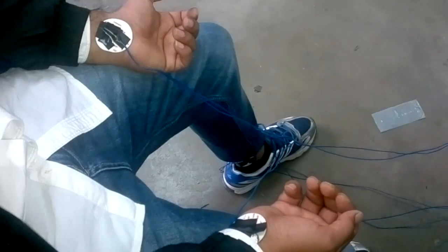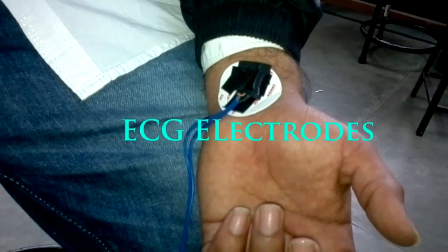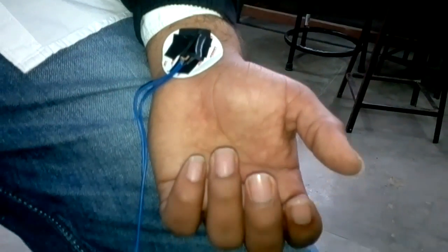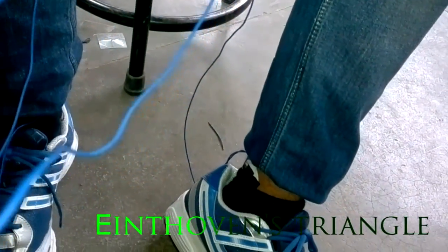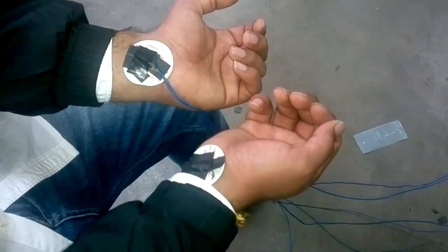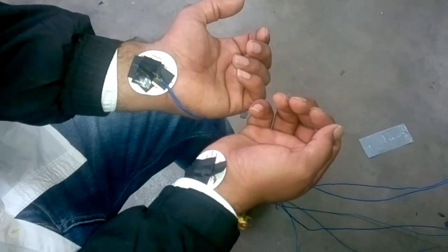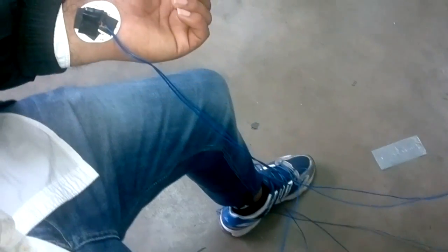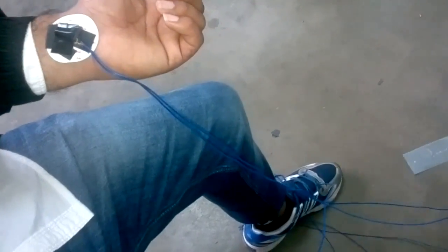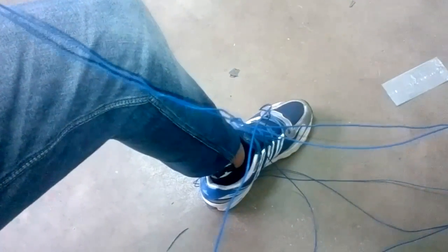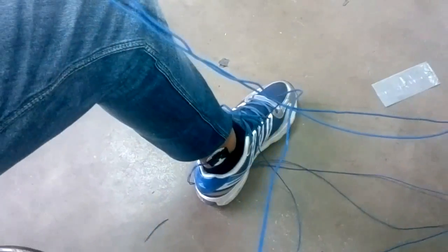Now describing each component. Special ECG electrodes have been used that can sense the weak signal from the patient's body. These electrodes are arranged in the form of an inverse triangle. The arrangement is being shown. In lead 1 arrangement, the positive electrode is connected to the left arm and the negative electrode to the right arm. For lead 2 arrangement, the negative electrode is connected to the right arm and the positive electrode to the left leg. Similarly, for lead 3 arrangement, the positive electrode is on the left leg and the negative on the left arm.